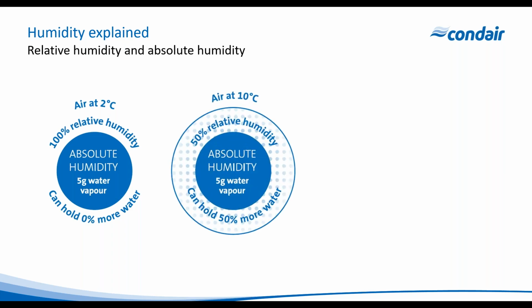Now, if we increase the temperature to 10 degrees C, well, now the air is expanded, it can hold twice as much water, but the absolute moisture content has stayed the same. We haven't put any moisture into the air or taken any moisture out of the air, but the percentage saturation has fallen to 50%. And the actual level of moisture in the air we call absolute humidity. So there is a huge difference between absolute humidity and relative humidity. Absolute humidity is the amount of water vapor in the air by weight, and relative humidity is the percentage saturation of air.